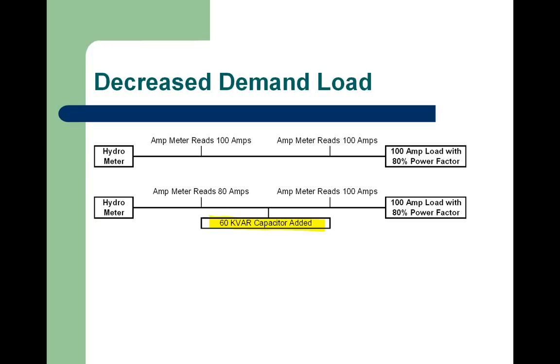Demand being, as a facility, the utility will supply you whatever number of kVA or kilowatts that you require as you demand. So your hydro bill would be based on consumption, which is the total amount of energy that you've used in a one month period, plus a billing demand, which is the highest amount of kilowatts or kVA that you have used over a 15-minute window.